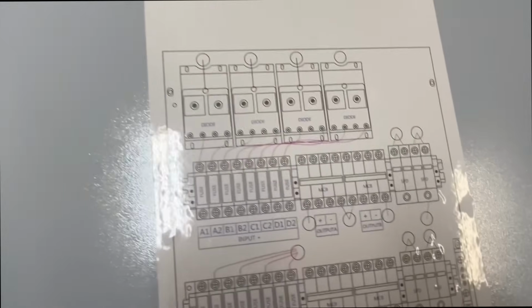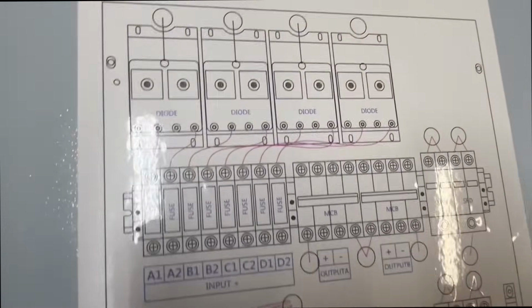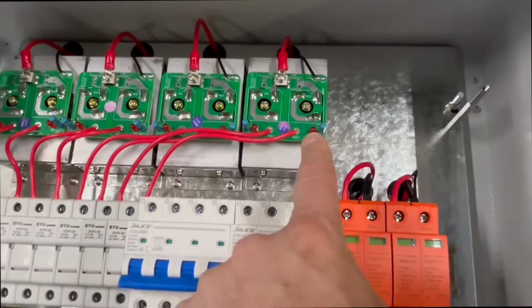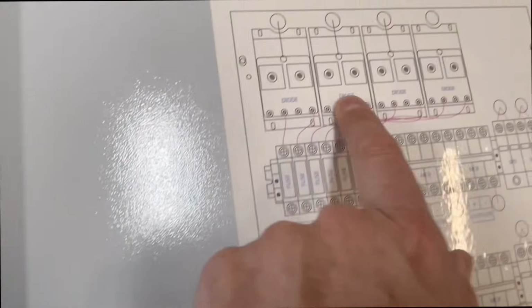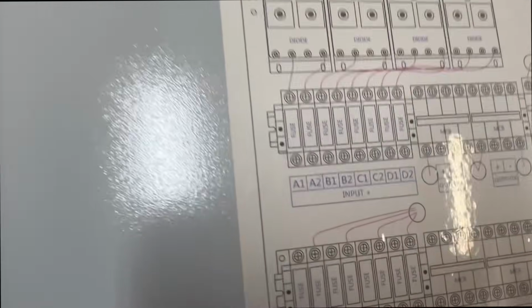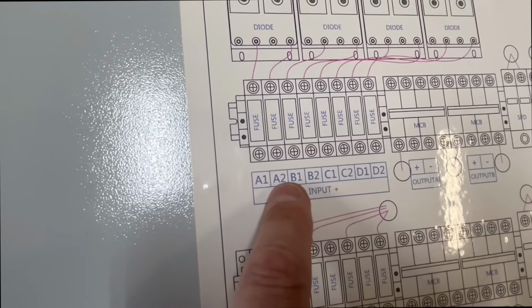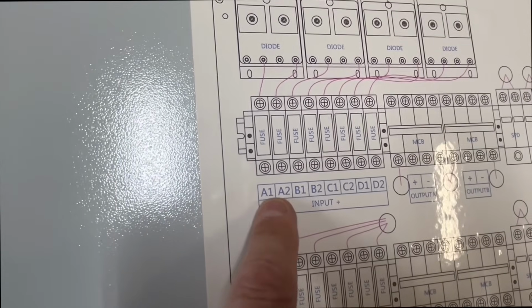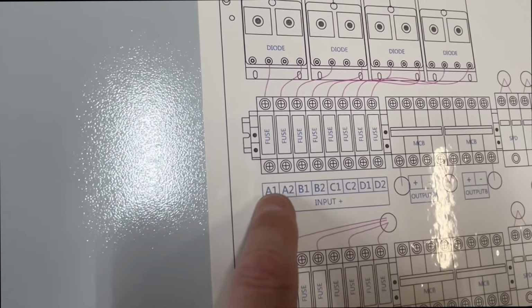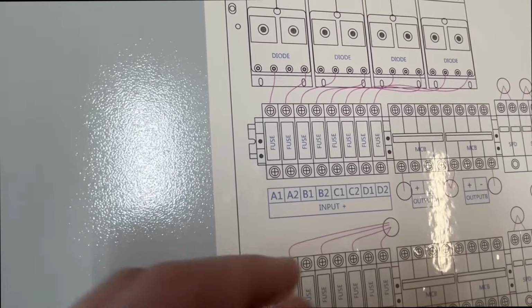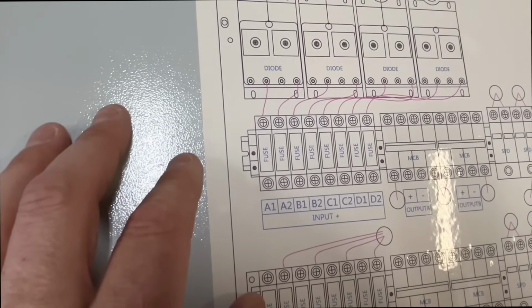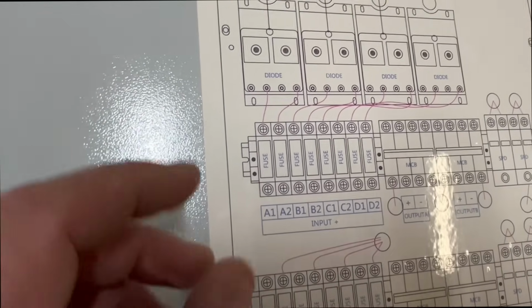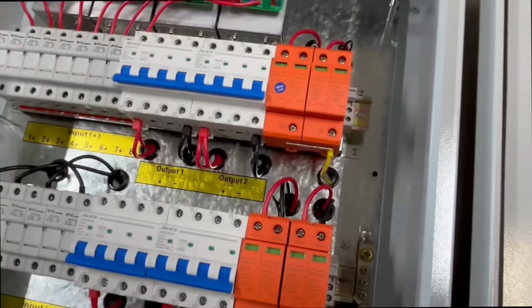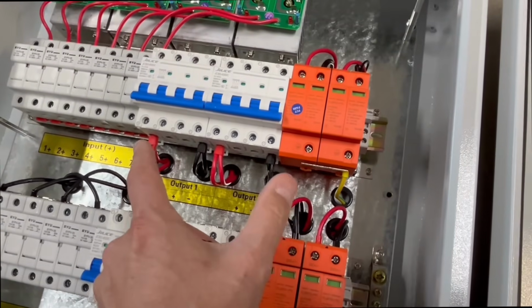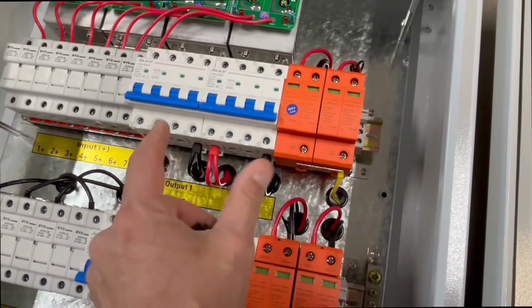All these combiner boxes are going to come with a map and they're going to show you exactly what's going on here. Up top, you can see these are diodes and it even describes that here on the map. And then it shows you A1, A2. This is where your first strings are going to come in to the unit. So let's say you've got two 3,500 watt strings coming in from a solar array, and you want to combine them in here. This gives a safe way to combine the two strings into one string.